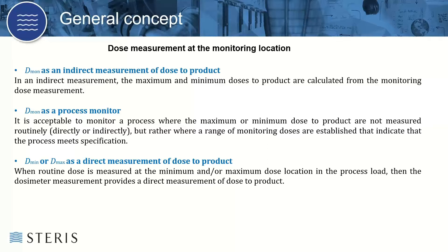A combination of these components can be used to determine the maximum and minimum dose targets for the routine monitoring dose. For process monitoring, it's basically using dosimetry at locations not on the product to monitor the process. In this situation, the variability associated with the measurement of minimum and maximum doses for PQ, combined with other relative components of uncertainty, can be used to determine minimum and maximum dose targets for the routine monitoring. Direct measurement means placing dosimeters throughout the product load at minimum and maximum dose locations determined during PQ mapping, and can also be used as an indicator that the process is in a state of control.